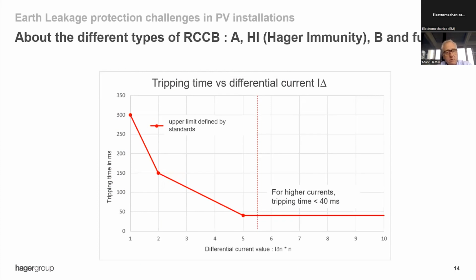What is important to know is when we speak of tripping times, so I mentioned 40 milliseconds and I mentioned 200 milliseconds, this is for the nominal differential current. And here we are speaking of 30 milliamps. This is our nominal differential current. Here you see on this diagram, you have the tripping time in milliseconds on the vertical axis, and on the horizontal axis, you have a ratio going from 1 to 10. 1 is 1 time the nominal differential current, so it's 30 milliamps. 2 is 60 milliamps. 3 is 90 milliamps, etc.